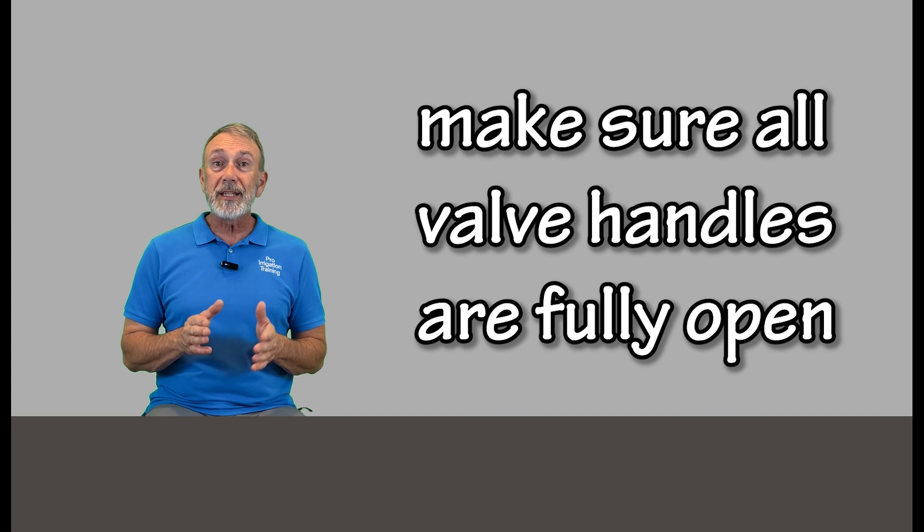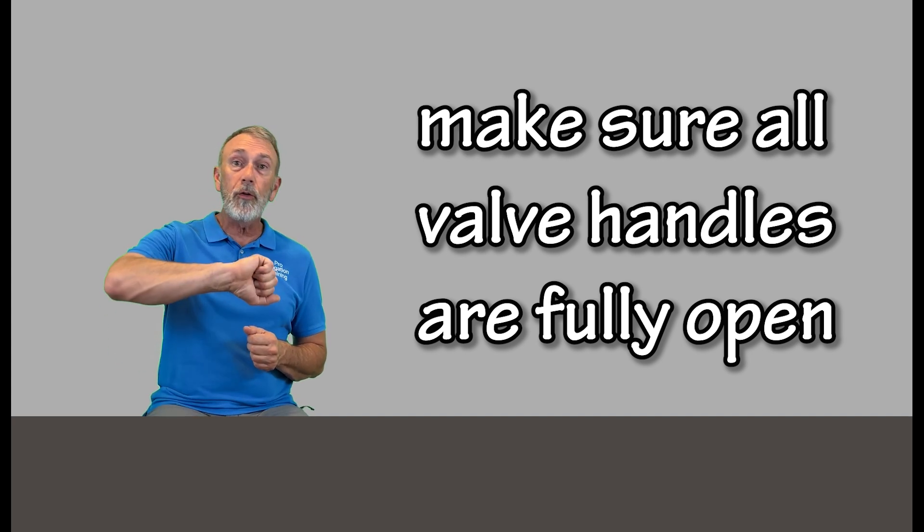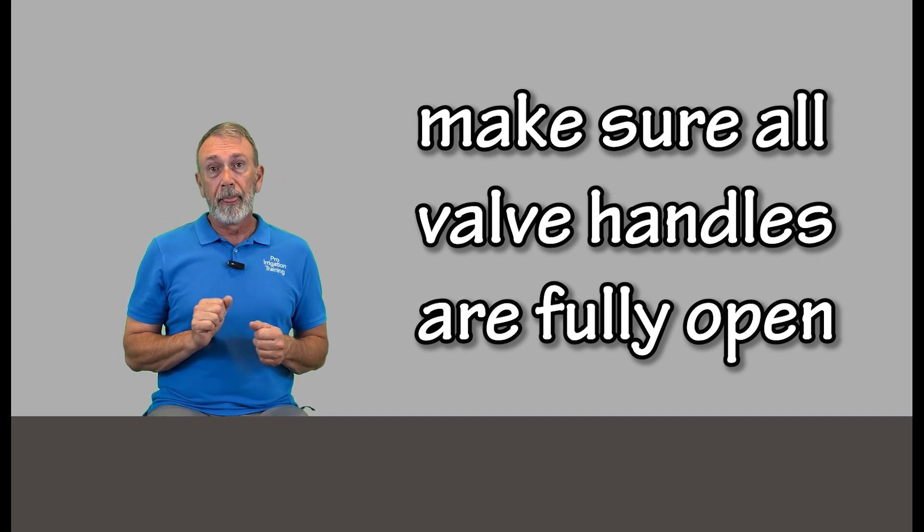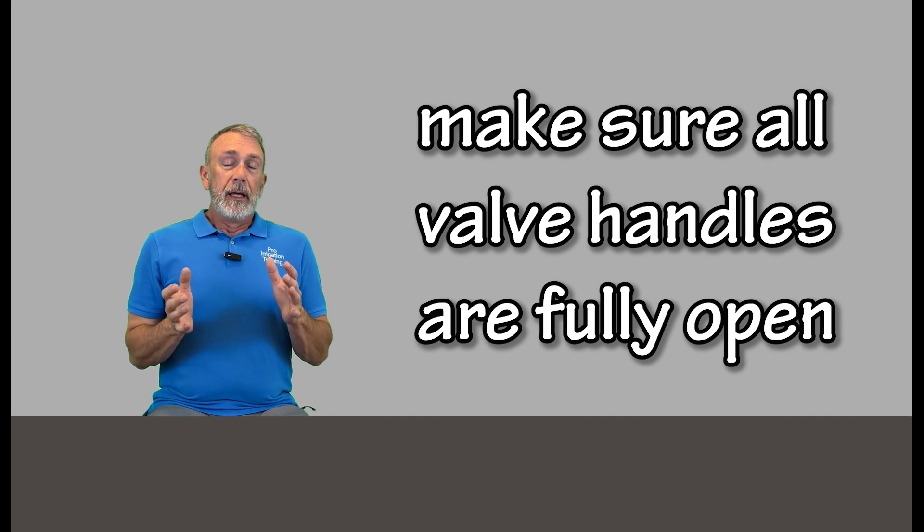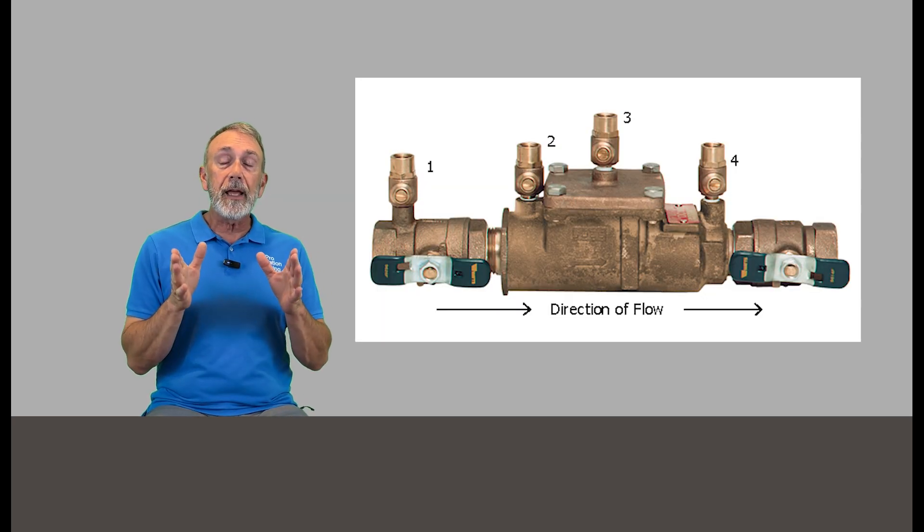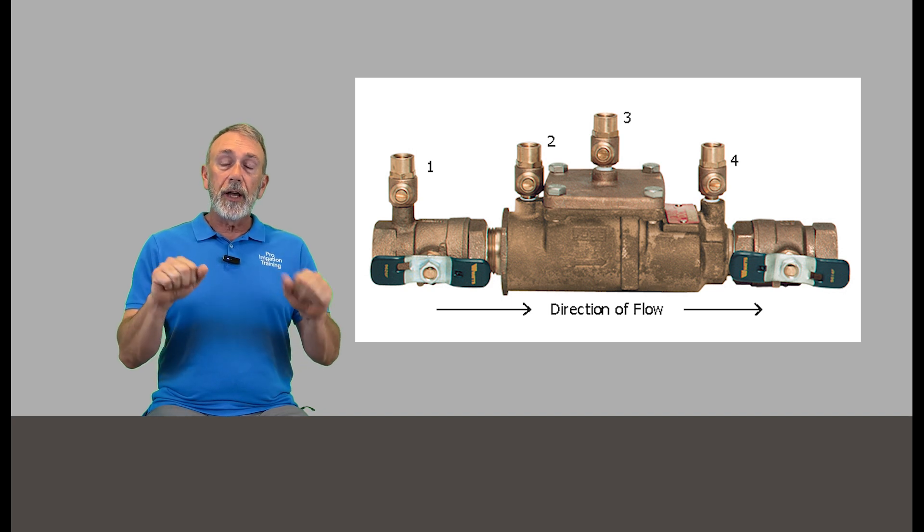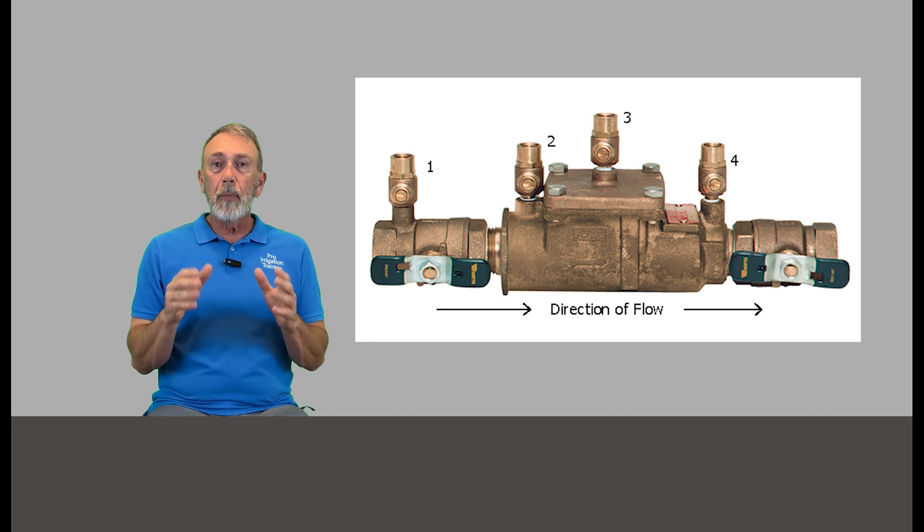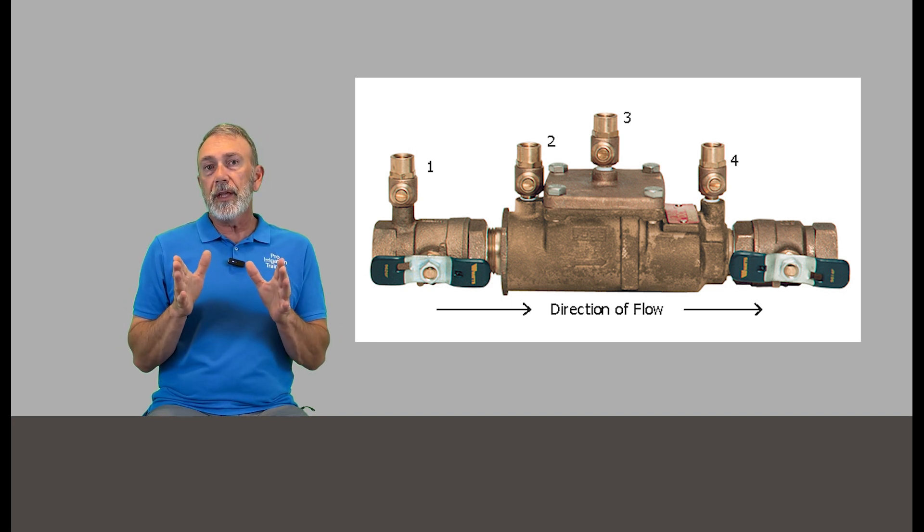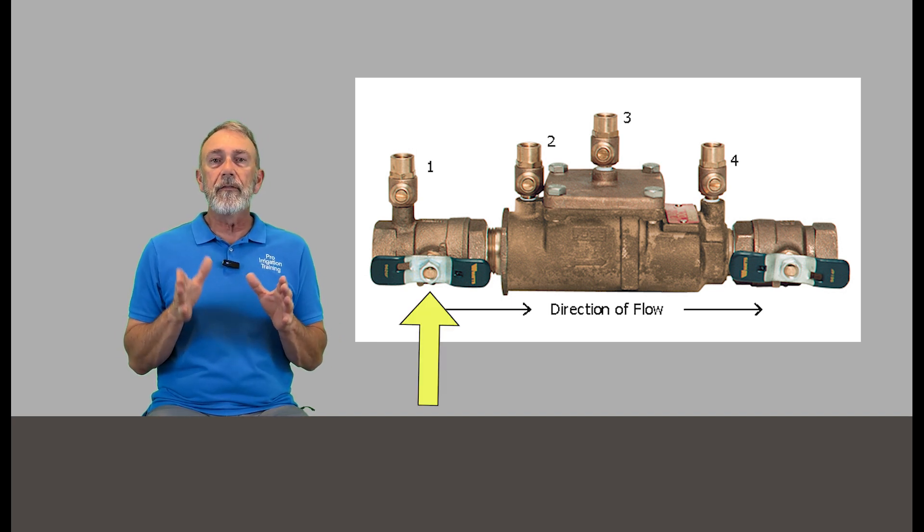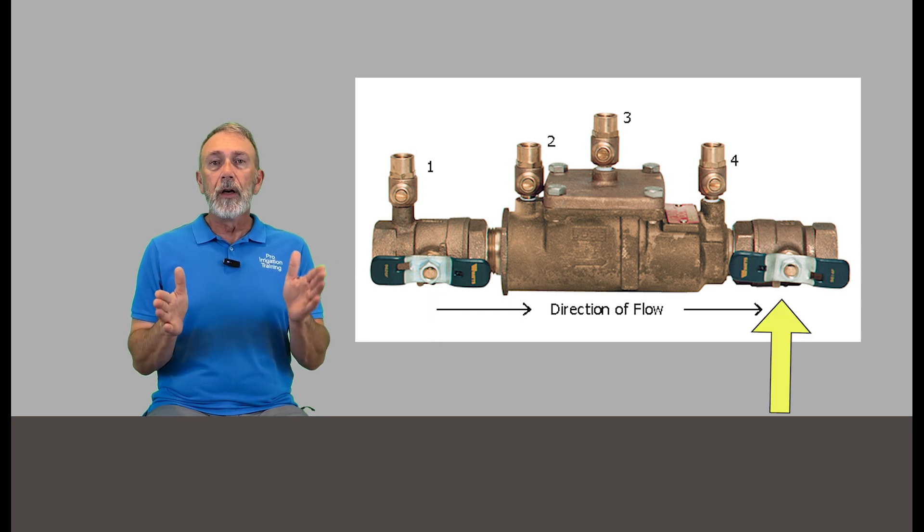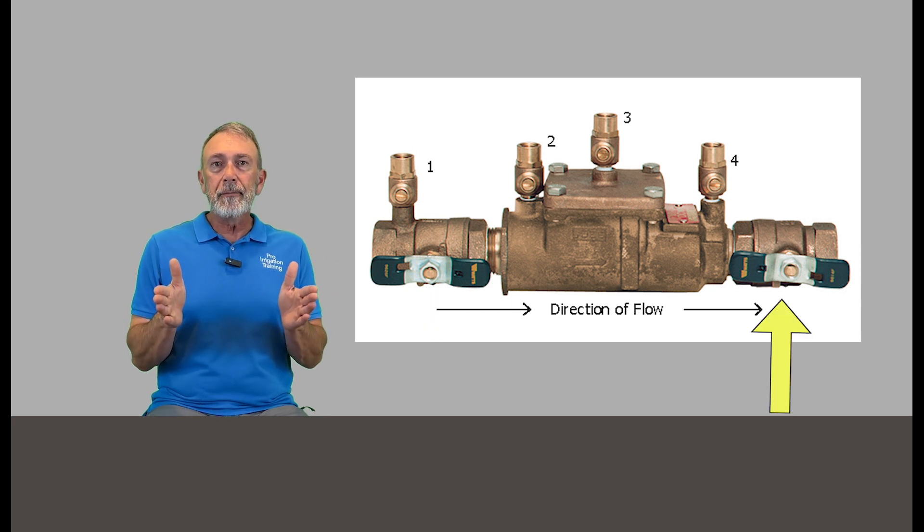Now we're going to go to our meter and our backflow preventer and see if all of the valves are all the way open. If you have a meter key, take it to the meter or curb stop, make sure it's fully open. Go to your backflow preventer and check both of the shutoff valves. Most of the backflow preventer types have a valve on each side, a shutoff valve for testing. Either one of those can shut the system off, but they're both there for testing.